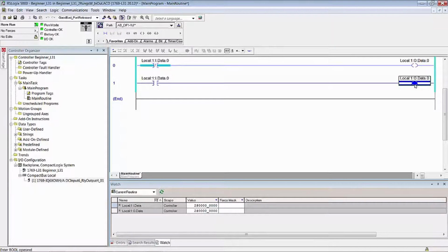And in this case, we have I/O getting updated in between rung 0 and rung 1. In order for this bit to be on, then after the scan of rung 0, the output gets updated and told that it's on, and then this rung gets executed and it's told it's off. But it doesn't tell it that it's off until next time around. And maybe it hits it just right, so it's updating the output right here. Execute rung 0, update outputs, execute rung 1, execute rung 0, update outputs, because it's every 20 milliseconds. I hope you get that.